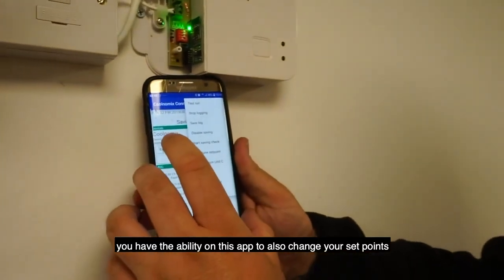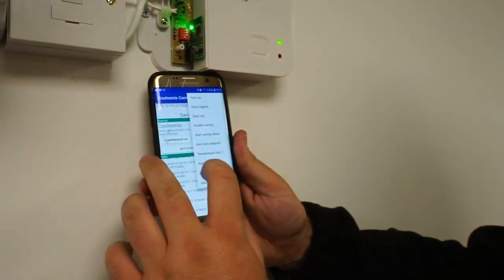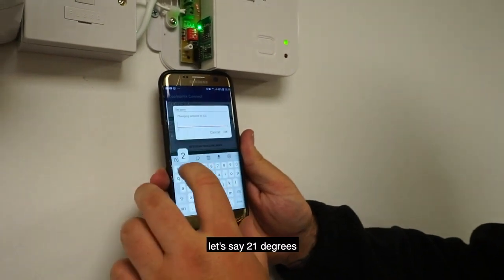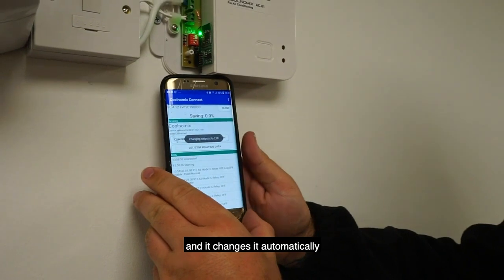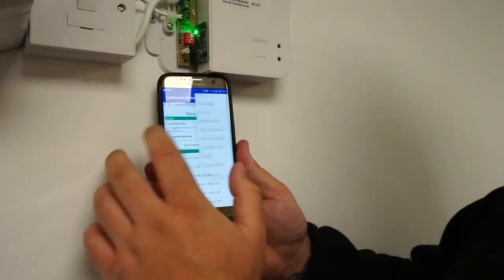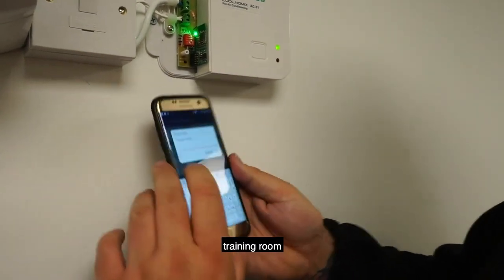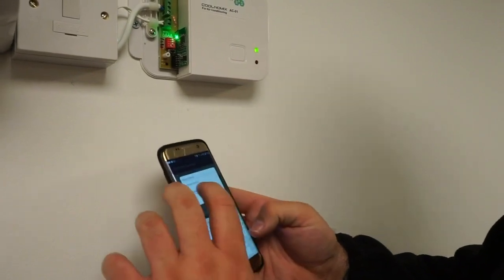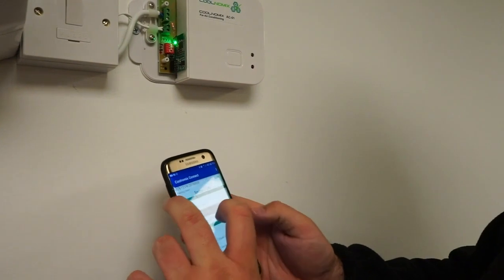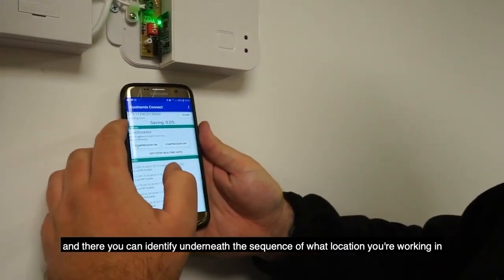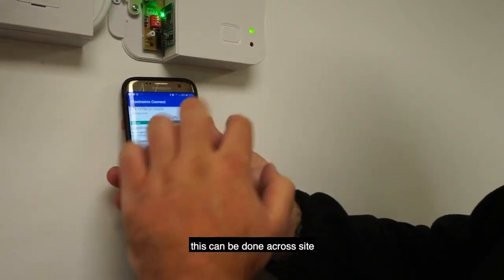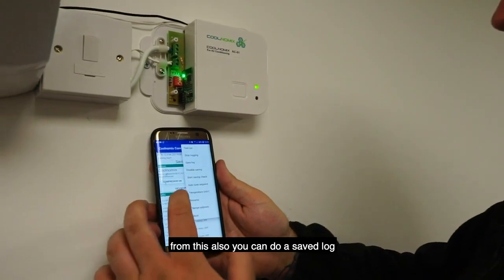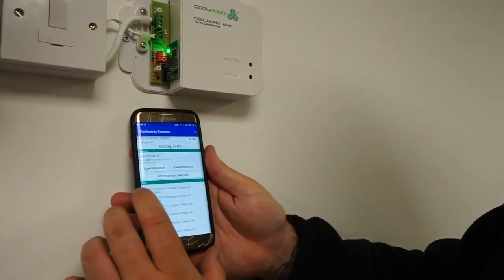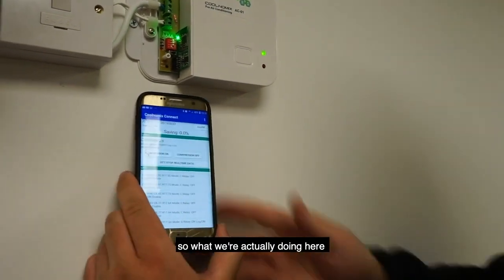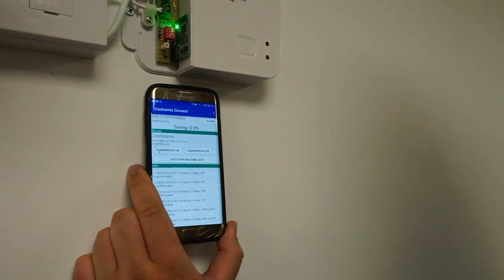You have the ability on this app to also change your set points. So you can change the set point at any time. Let's say 21 degrees, and it changes it automatically. This is good for a service tool once the system is actually installed. You can also rename it for training room. And now you can identify underneath the sequence of what location that you're working in. This can be done across site. From this also, you can do a saves log. So I'm doing test run. So what we're actually doing here is resetting the Coolnomix system and making sure that it works.